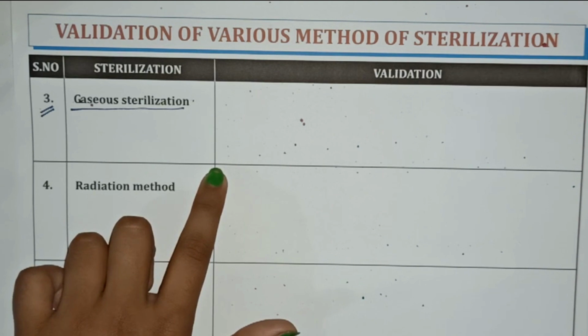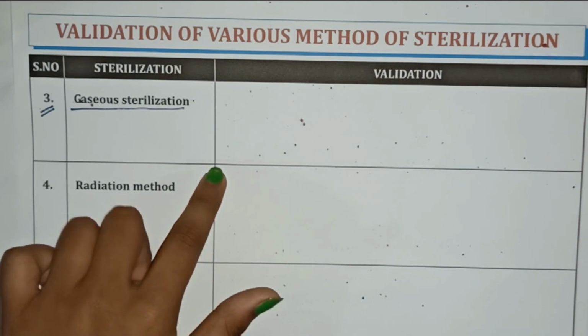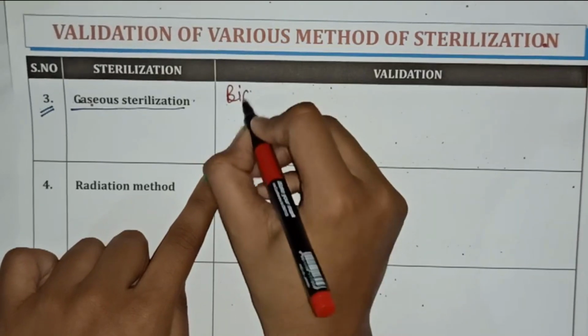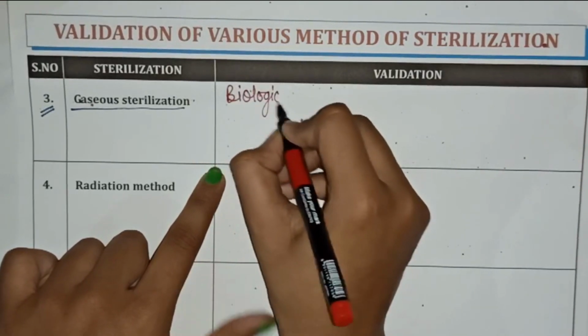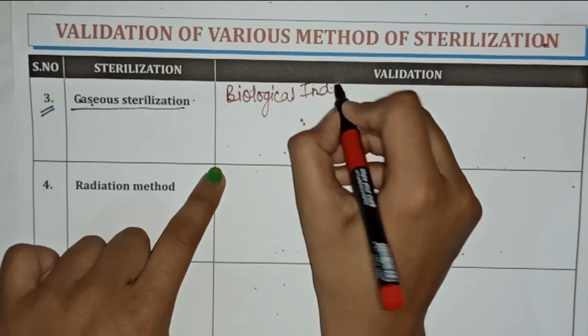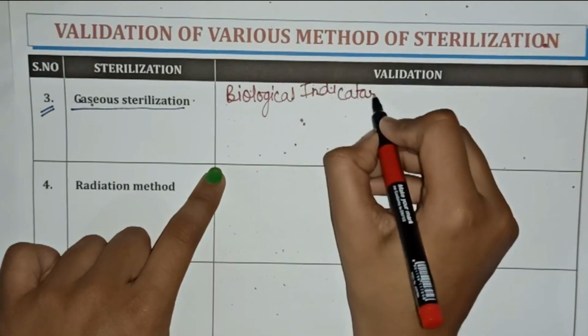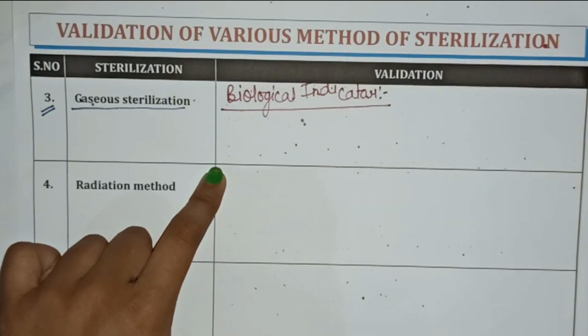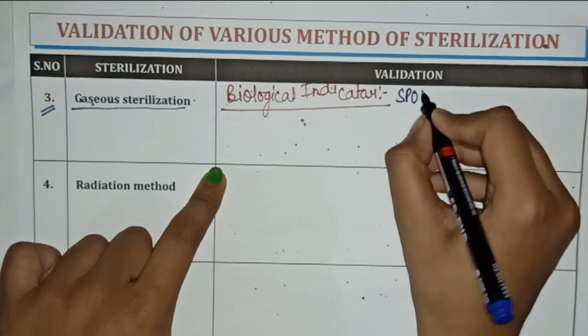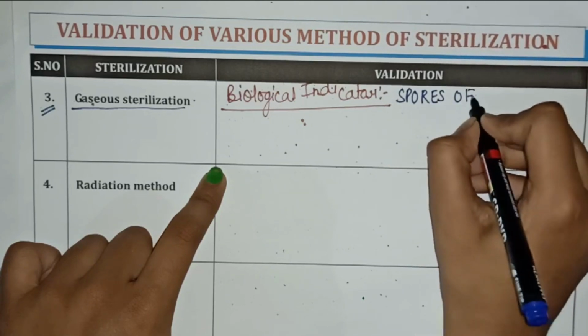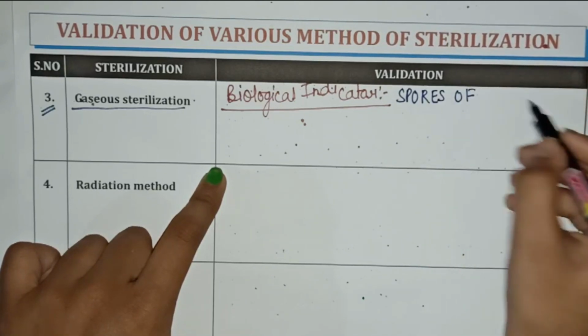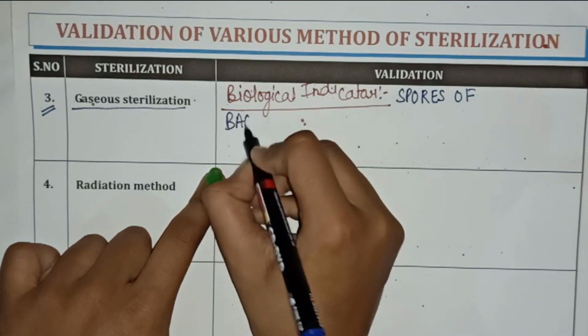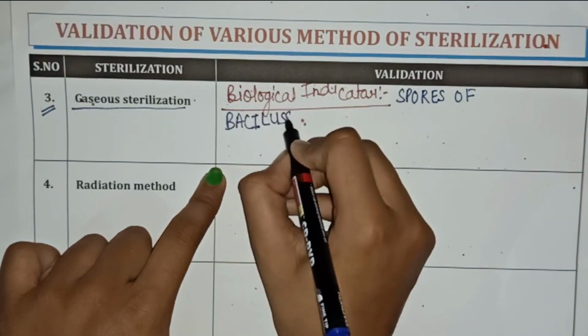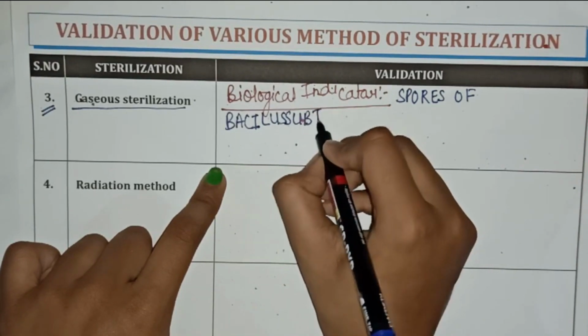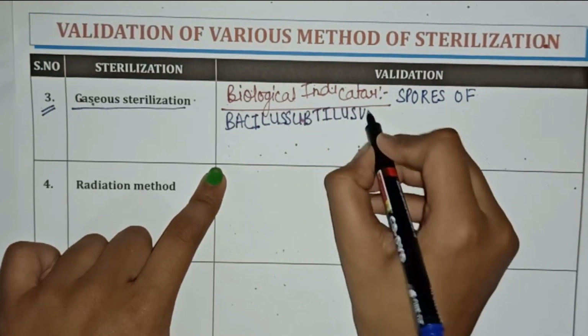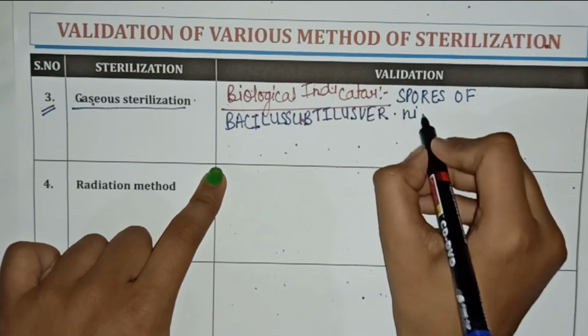The validation of gaseous sterilization requires biological indicators, that is spores of Bacillus subtilis var niger.